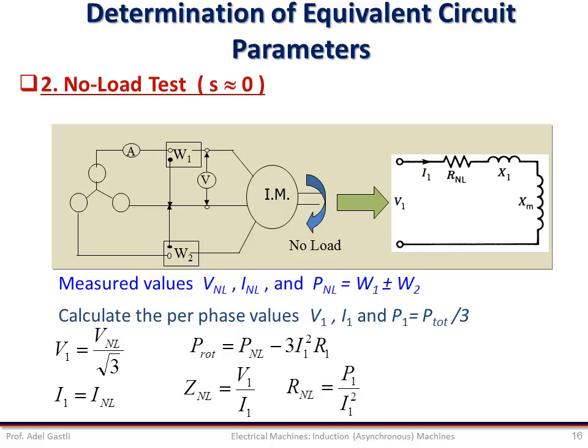Finally, the equivalent no-load reactance can be deduced from the calculated total impedance and the resistance. Note that this no-load reactance is actually the sum of the stator winding leakage reactance X1 and the magnetizing reactance XM. We cannot separate them at this moment, but we will come back to this expression later.